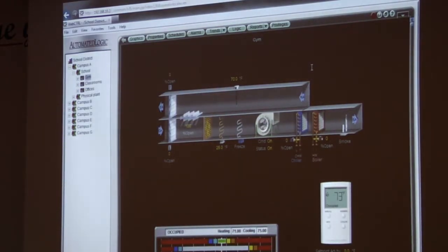Okay? Because I may have a bad return air temperature on one of your air handlers or your RTU. And I'm going to show you in logic that if your return air temperature isn't working or it breaks and it reads negative, it forces our software freeze safety to kick in, and it closes your dampers and it opens your valves halfway. All right? So you will be doing the exact same thing that you're doing here right now. You're going to come into a graphic and go, does this look normal? And if it doesn't, you have to go through each point and start to find out why it doesn't look normal.